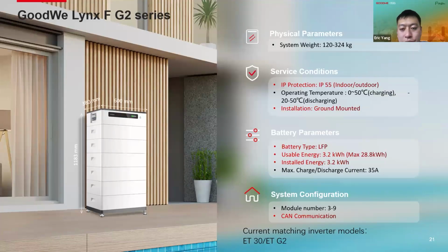And this is the GoodWe Lynx F G2 series, which is a high voltage battery that can work with the GoodWe ET Plus series. The battery cell is LFP, and the usable energy of each battery module is 3.2 kilowatt hour. And the maximum can be 9 pieces. So each battery tower can be 28.8 kilowatt hour. The maximum charge and discharge current of this battery is 35 amps, so it can work with the ET Plus series, whose battery charge and discharge current is only 25 amp. The module number minimum is 3 pieces, so the minimum usable energy is 9.6 kilowatt hour, and the maximum is 9 pieces, which is 28.8 kilowatt hour.